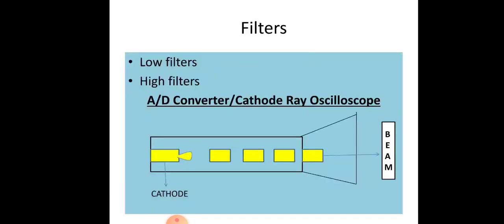Now coming to filters. I already told you it just passes on the signals. Even if they are amplified, even if the common mode rejection ratio is already present, some unwanted signals still pass through to the filters, wherein the filter removes the unwanted signals. What are those signals? The movement of the needle, if a needle electrode is used, the signals picked up by the fascia, the signals picked up by the tendon, the signals picked up by your skin. So all these signals we do not need. What we need in our study is only the signals of the muscle picked up by the electrode.